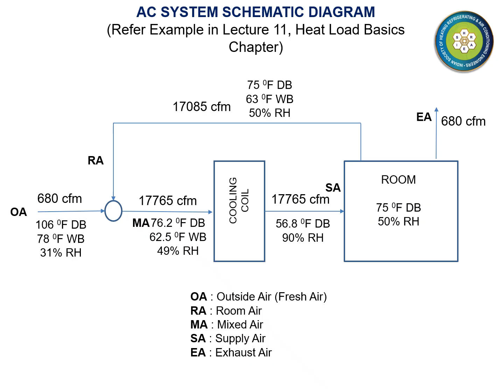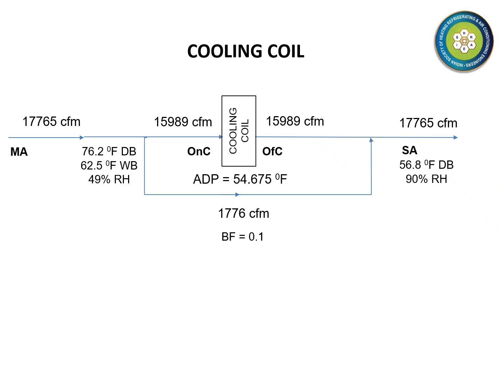Furthermore, the cooling coil's apparatus dew point and bypass factor were estimated at 54.67 degrees Fahrenheit and 0.1 respectively. The dehumidified air flow through the coil was estimated at 15989 CFM. The mixed air calculations are shown on this slide. Pause the video and go over the calculations carefully.